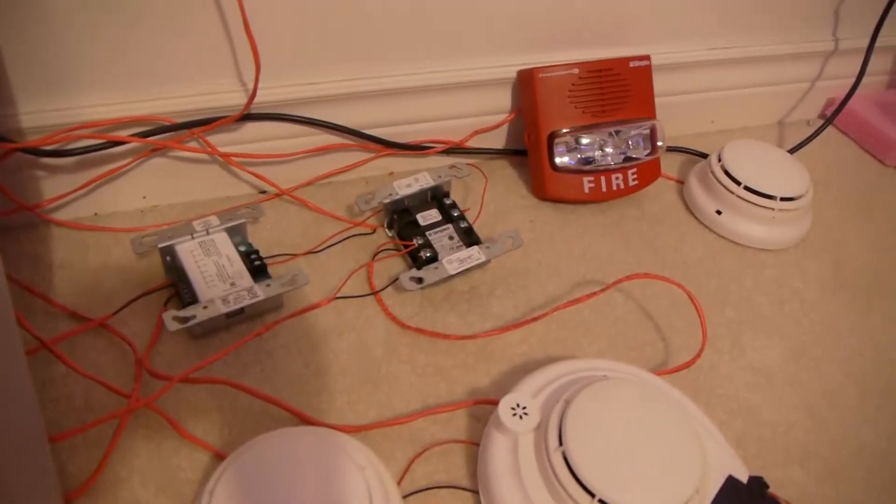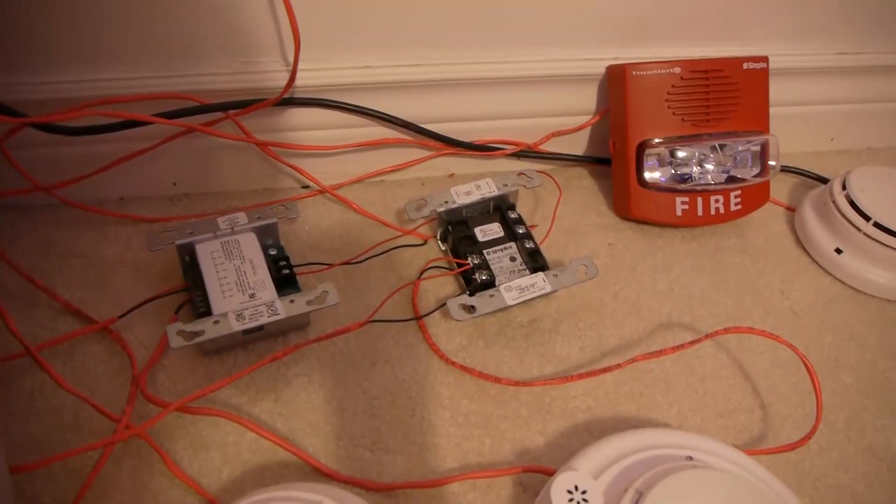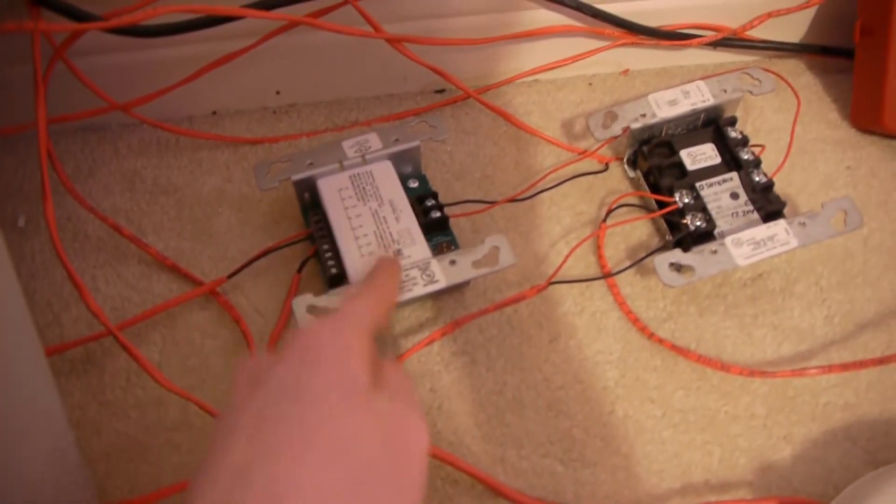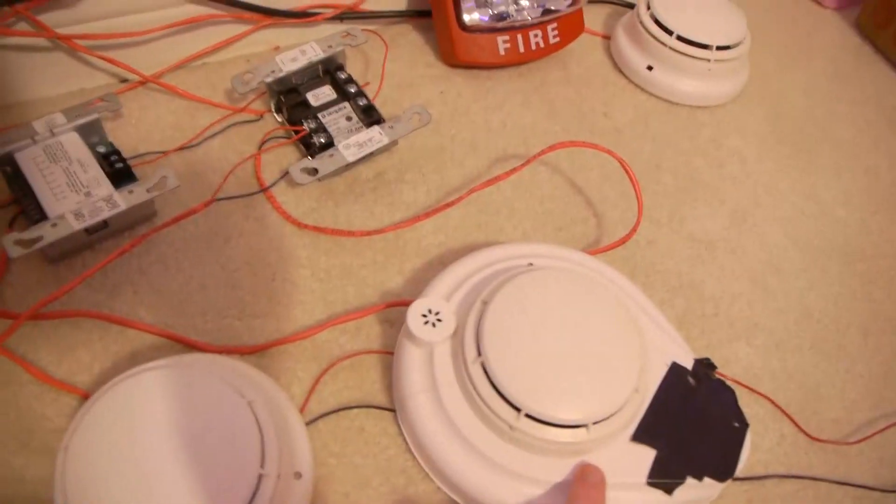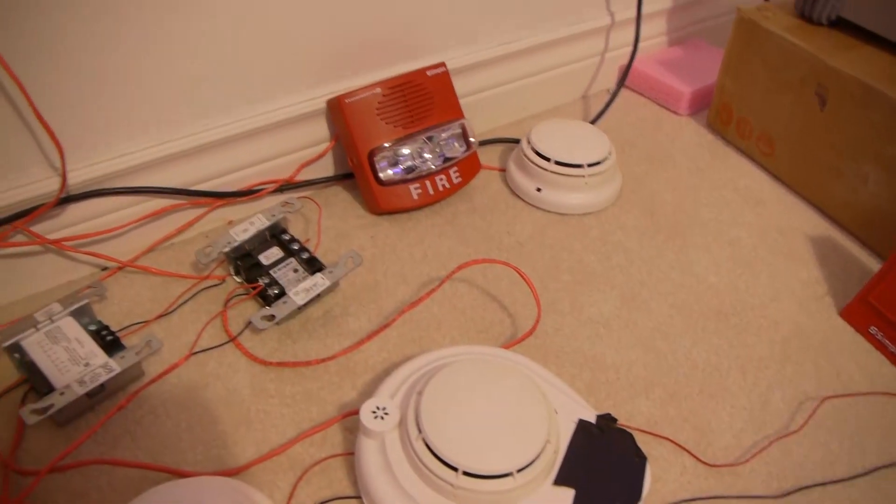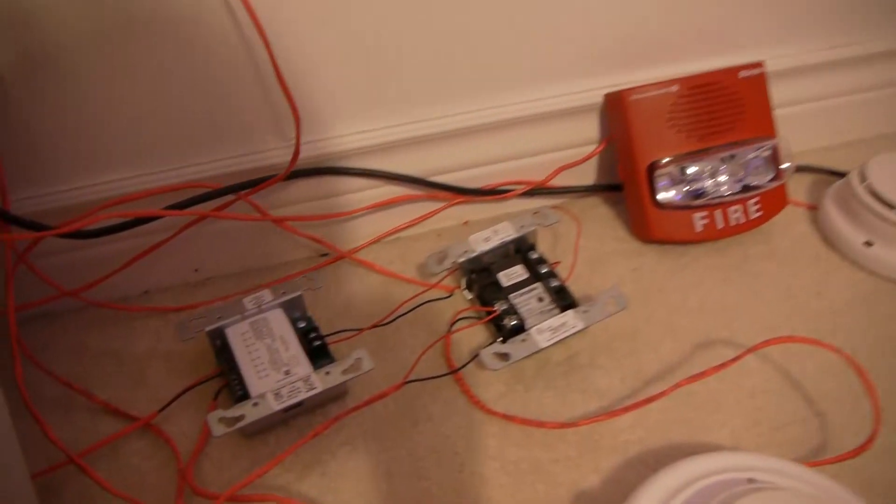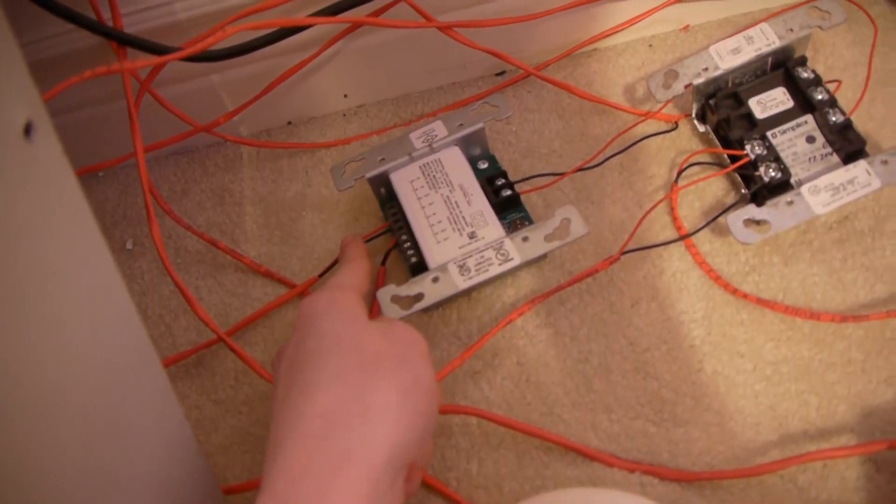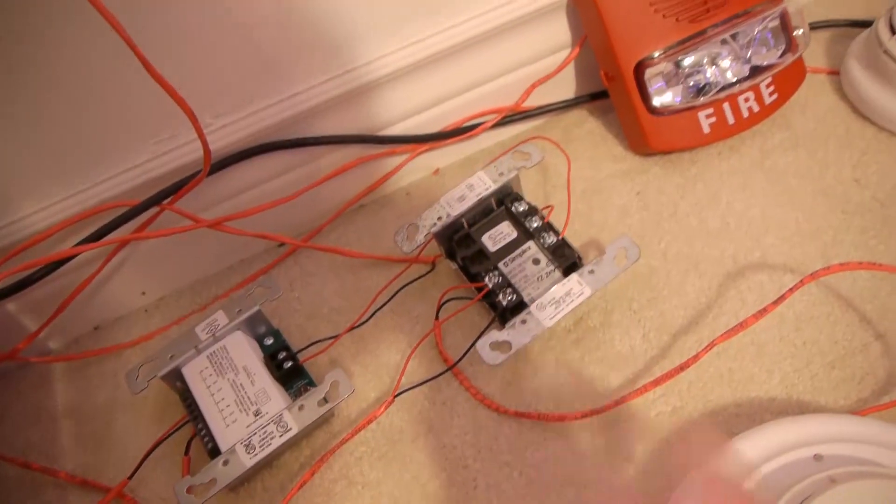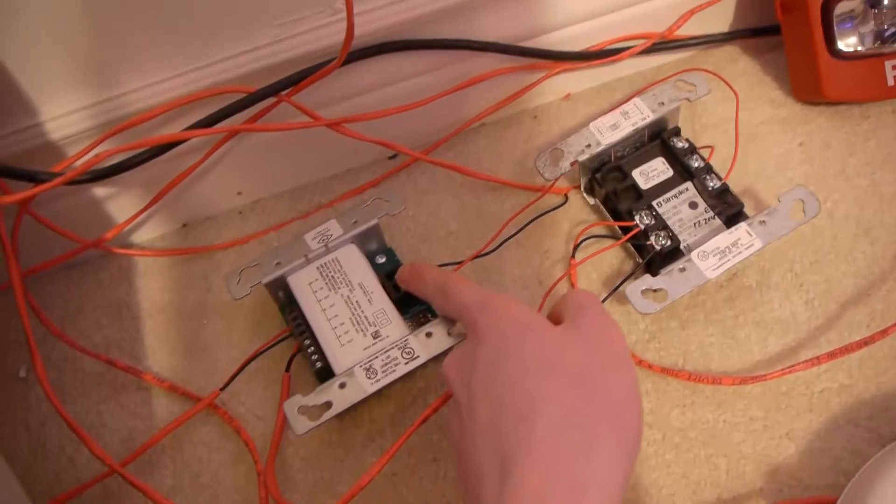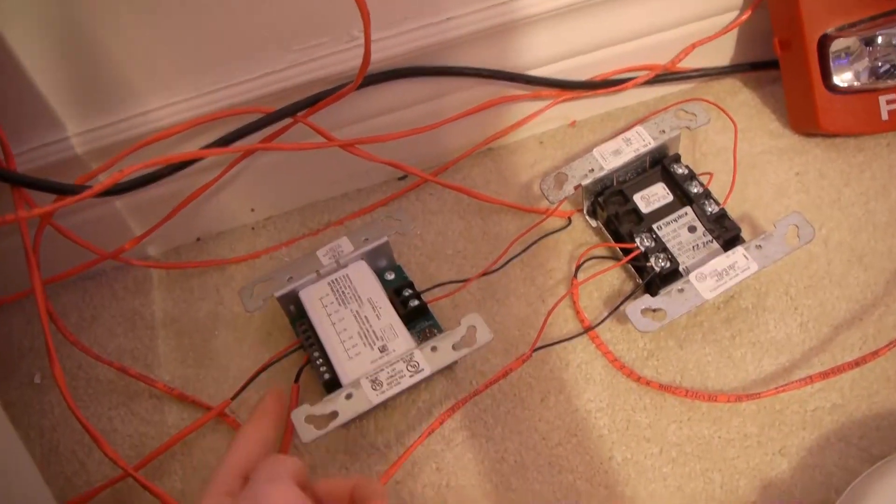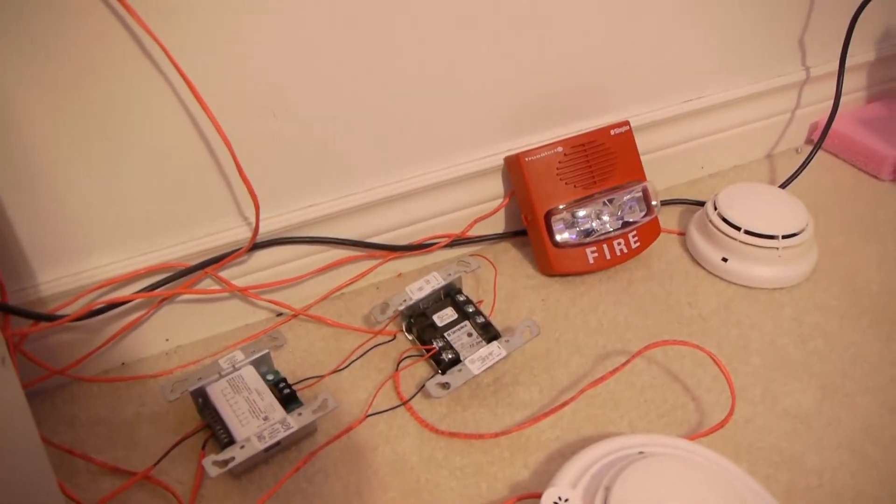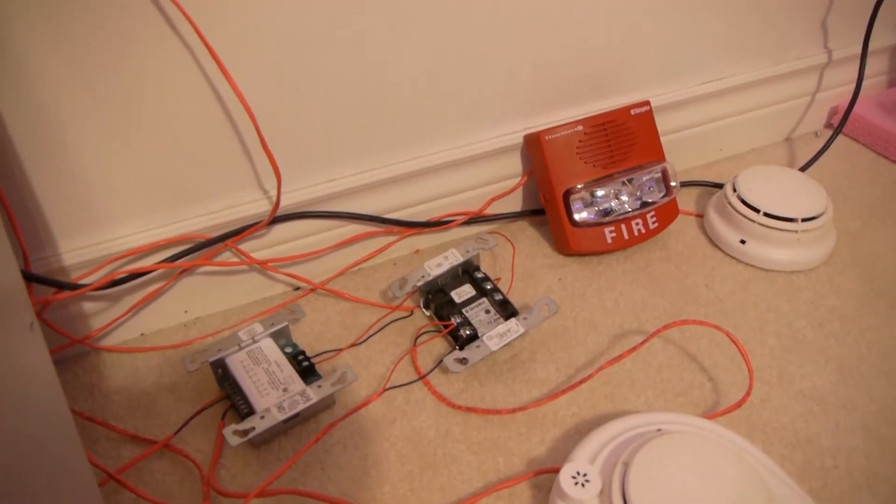Which I programmed to be an alarm relay basically. It has a lot of custom coding done to it, and it's called custom control, and that controls what the relay does when there's a fire or carbon monoxide event. But basically, that relay comes on if there's a fire, so basically power comes from that circuit through this module, you can kind of ignore the module for now. It basically just gets passed right through, and it goes to the sounder base. And the relay on the panel, you'll hear when we activate it, does a code 3, and that's what's coding the horn. Now if there's a carbon monoxide event, basically the panel will just feed steady 24 volt power into this. And then it will also, via this relay module right here, which would normally be done via a NAC circuit, but I don't have any on this panel, so I used a relay, will also feed power into this set of terminals on this code 4 module. And that will make the output code 4 to this horn. So basically, it's a complicated way of making it do code 3 for fire and code 4 for carbon monoxide.